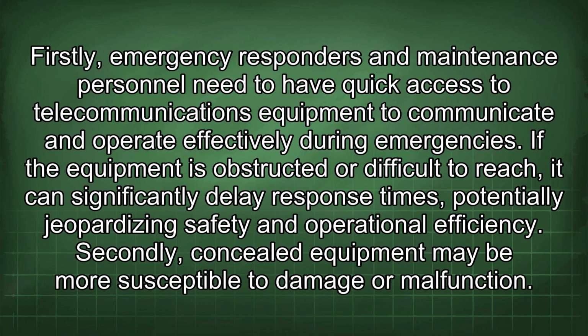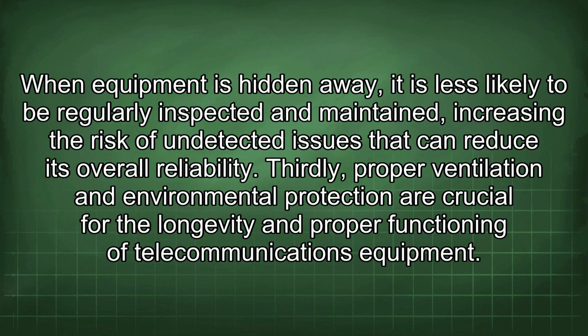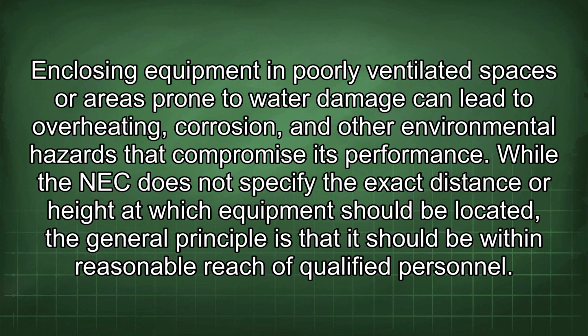Firstly, emergency responders and maintenance personnel need to have quick access to telecommunications equipment to communicate and operate effectively during emergencies. If the equipment is obstructed or difficult to reach, it can significantly delay response times, potentially jeopardizing safety and operational efficiency. Secondly, concealed equipment may be more susceptible to damage or malfunction. When equipment is hidden away, it is less likely to be regularly inspected and maintained, increasing the risk of undetected issues that can reduce its overall reliability. Thirdly, proper ventilation and environmental protection are crucial for the longevity and proper functioning of telecommunications equipment. Enclosing equipment in poorly ventilated spaces or areas prone to water damage can lead to overheating, corrosion, and other environmental hazards that compromise its performance.